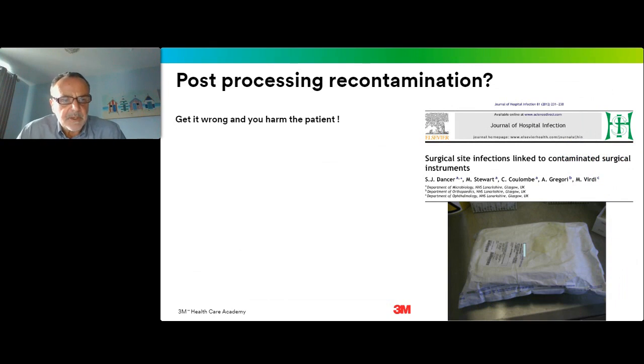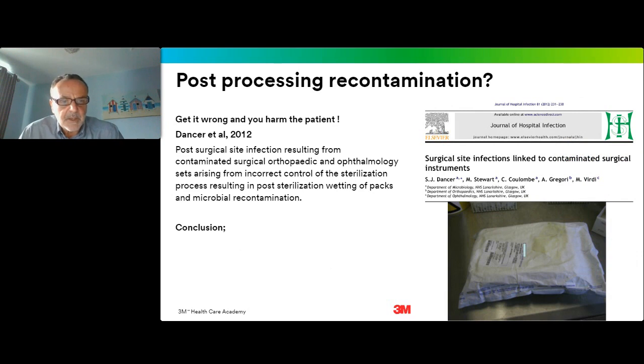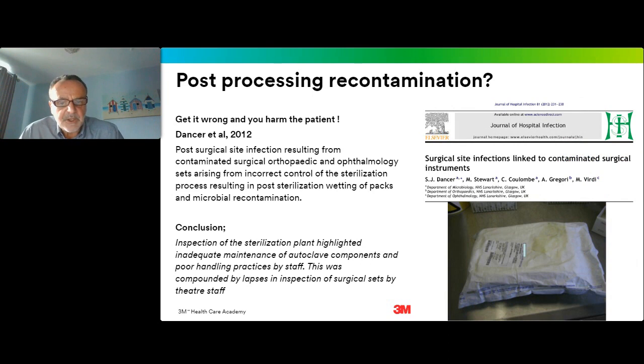So post-process recontamination is a major, major problem if it occurs. This is a paper written by Dancer in 2012, and she reports on a number of patients that had post-surgical infections, and when they carried out an investigation, they discovered that in the sterilizer, the packs, which you can see in the bottom right corner, were getting recontaminated with condensate that was being trapped in pipework and splashing onto the surface of the packs. You can see the staining there in the top right corner of this pack. That in turn was recontaminating the load items and allowing bacterial ingress into the packs, and that resulted in contamination of the loads, the instruments, and therefore, sadly, infection of patients. Luckily, there were no mortalities, but there were some quite serious infections.